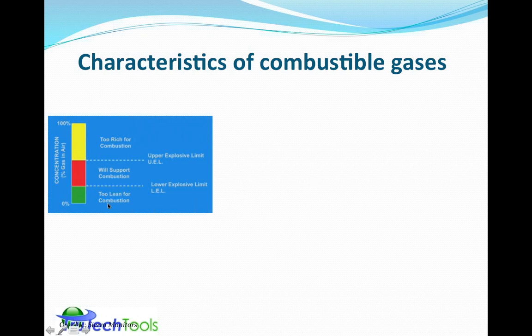And this little chart gives you an idea of what happens when you move from an area where you have too lean a mixture, or not enough fuel for the amount of oxygen present to support combustion with any kind of source of ignition. There's just not the right mixture there. When you come up to the first level, it's the lower explosive limit. That's the point at which you have just enough fuel and air mixture to create an explosion. And anywhere above that point, it will support combustion with a source of ignition.